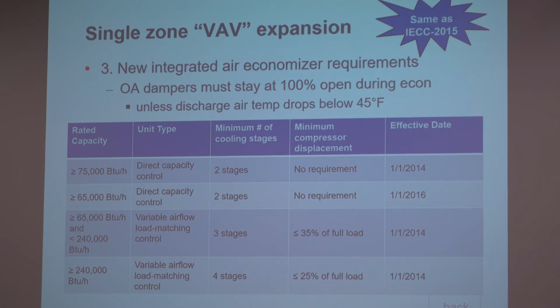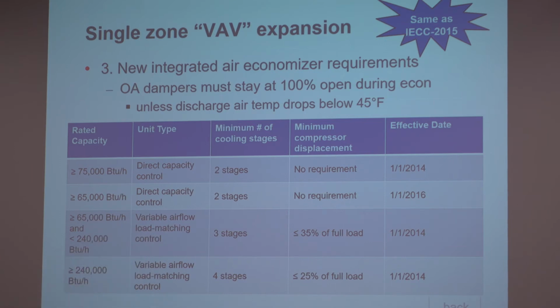Is there an exception for that? So the way that dehumidification limits work, this will actually help with dehumidification now. No, but we may have a space where we actually need higher humidity. We have some process, farm space. Not that I know of. I don't know that there's a specific exception that says you don't have to do this if your humidity requirements are such that you want it to be higher. I think you have better control of humidity altogether with this than you would have had without it.